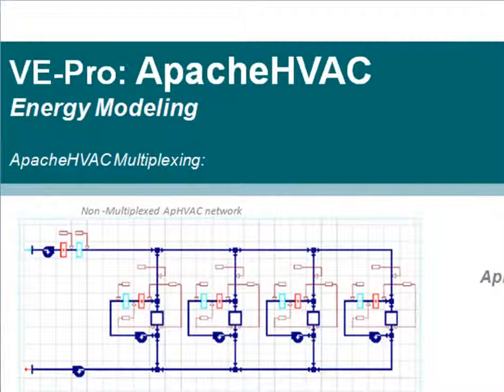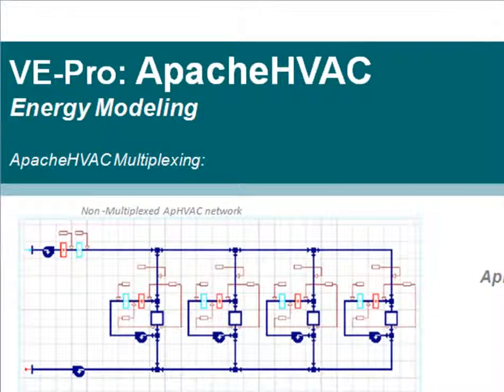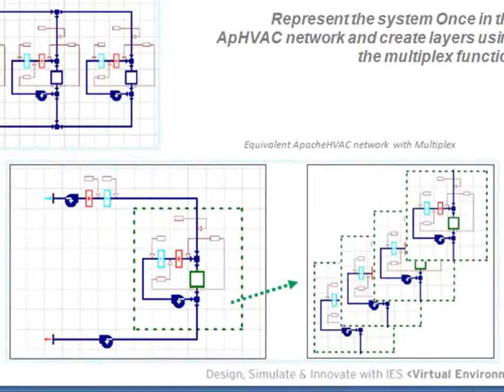In the top image of this slide you can see a four zone network with fan coil units for each zone and a common outside air system. Without the multiplexing feature, each fan coil unit and zone has to be represented in the network, leading to very large networks that are a nightmare to edit. With the multiplexing feature this is all avoided. You can represent the common outside air system and create one fan coil unit representation in the network.